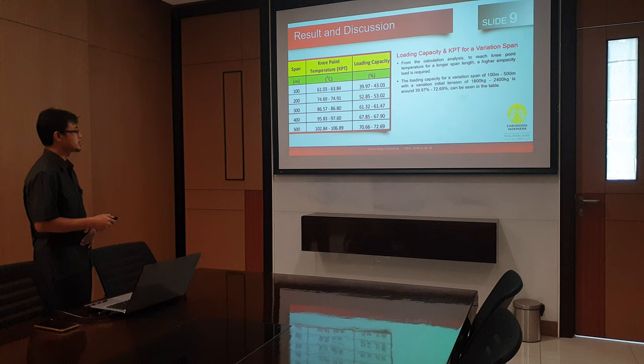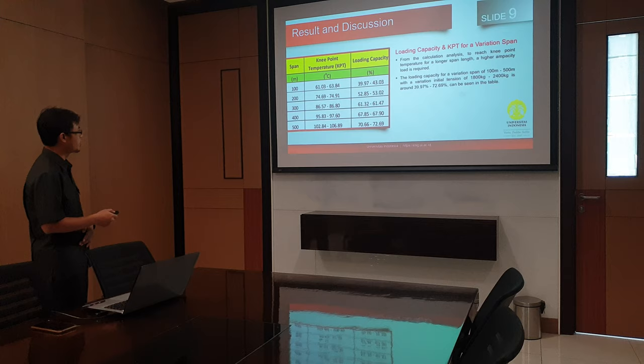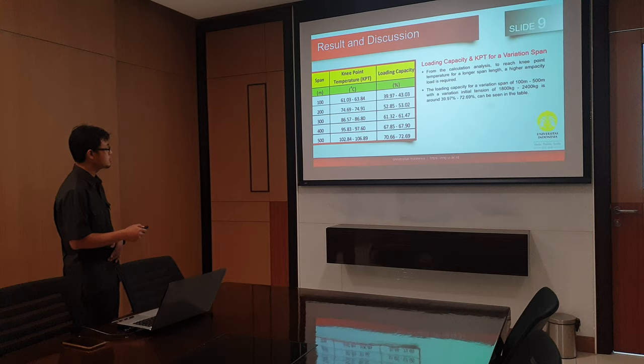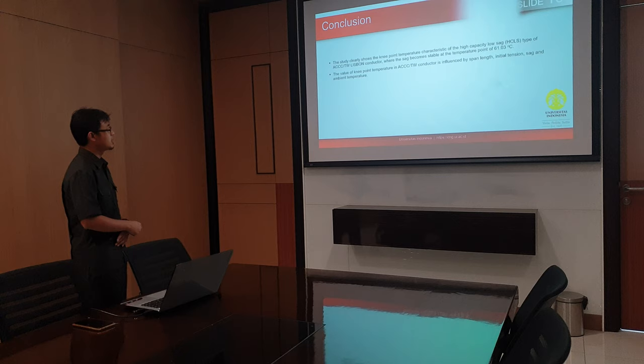From this calculation analysis, to reach the Knee Point Temperature for a larger span, a higher ampacity load is needed. The loading capacity for a variation of span from 100 m until 500 m, with a variation in initial tension from 1,800 kg until 2,400 kg, is around 39.97% until 72.69%.